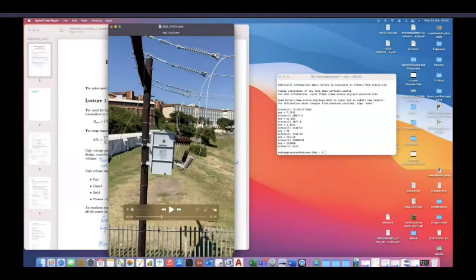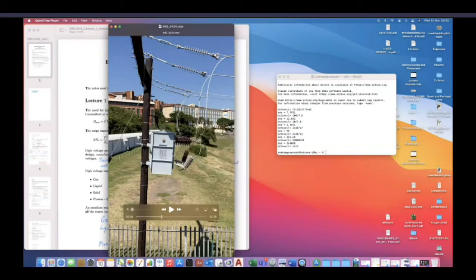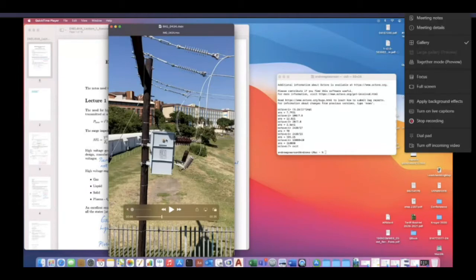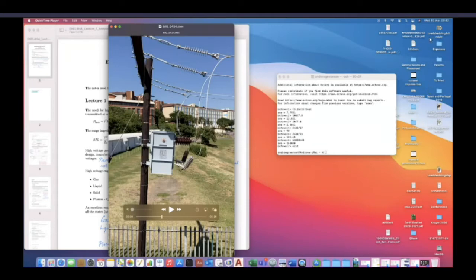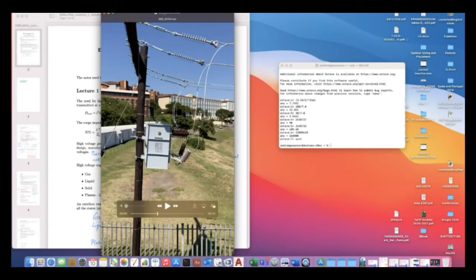Right, this device here looks like a big metal box. Inside that big metal box, there's a medium voltage transformer. We can't see much of that, but you would have studied that in Design 3, what goes on inside there. Right here is a bushing. Somehow we need to get the high voltage out of the transformer onto this conductor. It doesn't look like a very big gap between the conductor and the hole there. So the bushing is used to insulate the conductor coming out of the transformer. It prevents the conductor touching anything. It is a mechanical thing, so it is mechanically keeping that conductor stable.